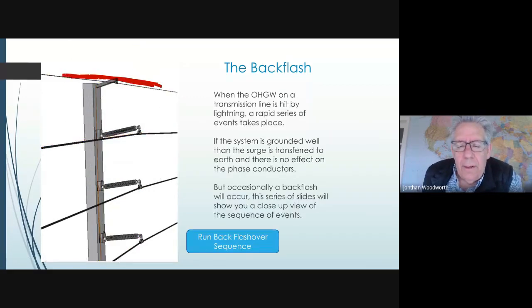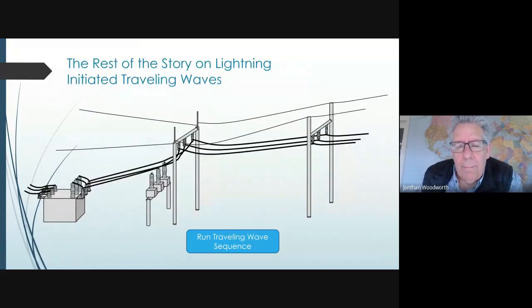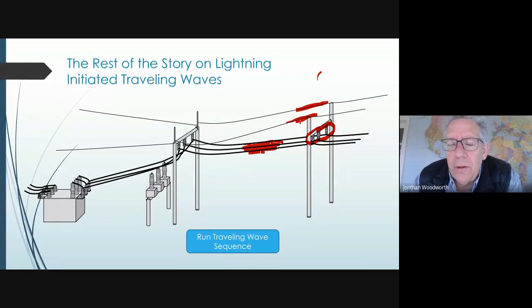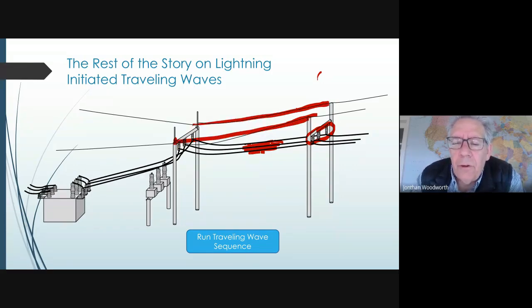So that is the sequence of events when there's a shield on the transmission system. I haven't mentioned this before, but you can see in this video, on this slide here, this transmission line has insulators here. It has the phase conductors, usually 3 of them, but it has these 2 fine wires on the top that go from pole to pole, and this is called a shield wire.